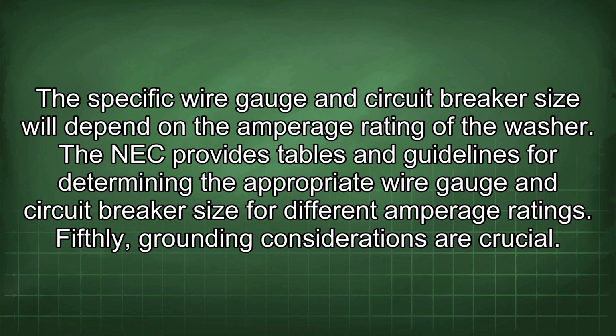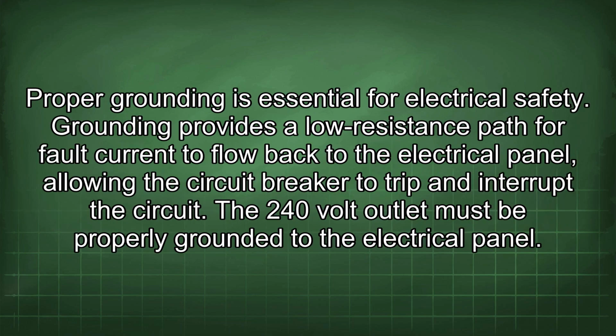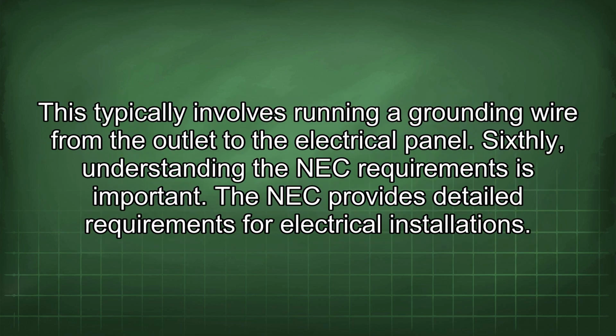Fifthly, grounding considerations are crucial. Proper grounding is essential for electrical safety. Grounding provides a low resistance path for fault current to flow back to the electrical panel, allowing the circuit breaker to trip and interrupt the circuit. The 240 volt outlet must be properly grounded to the electrical panel. This typically involves running a grounding wire from the outlet to the electrical panel.